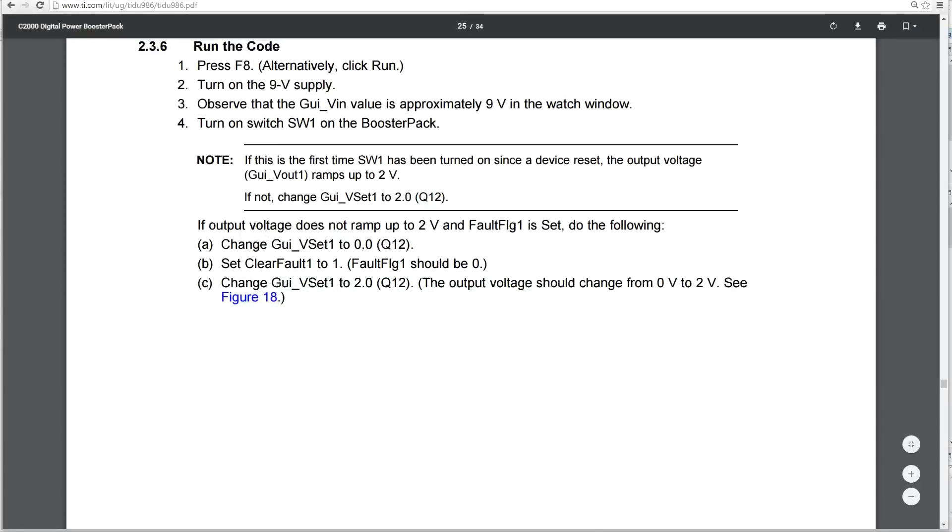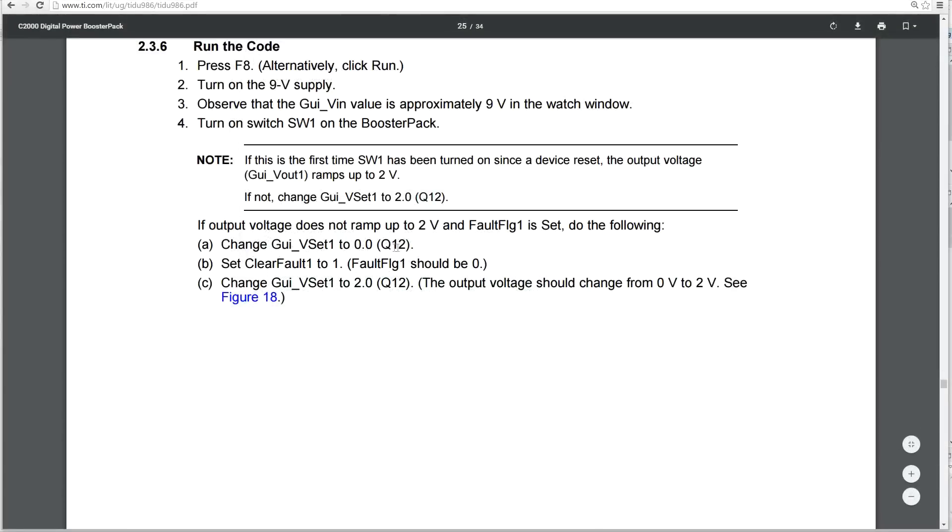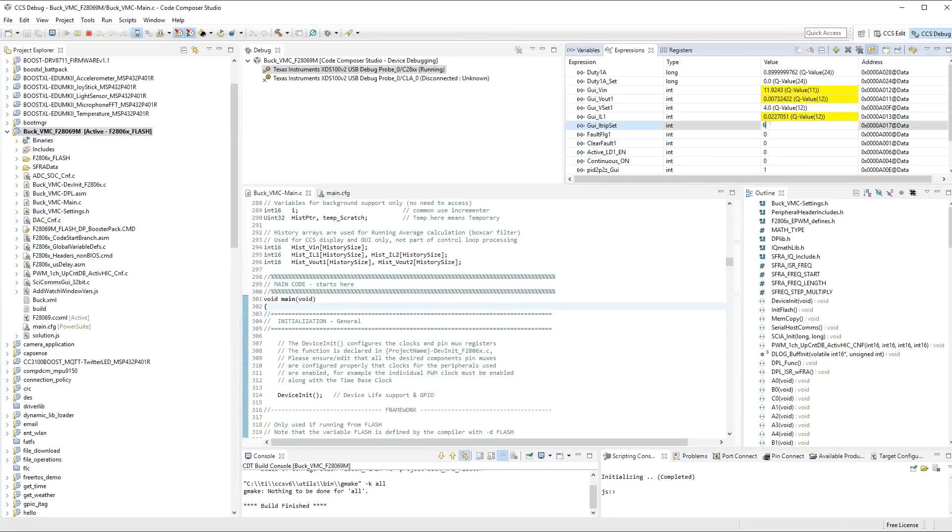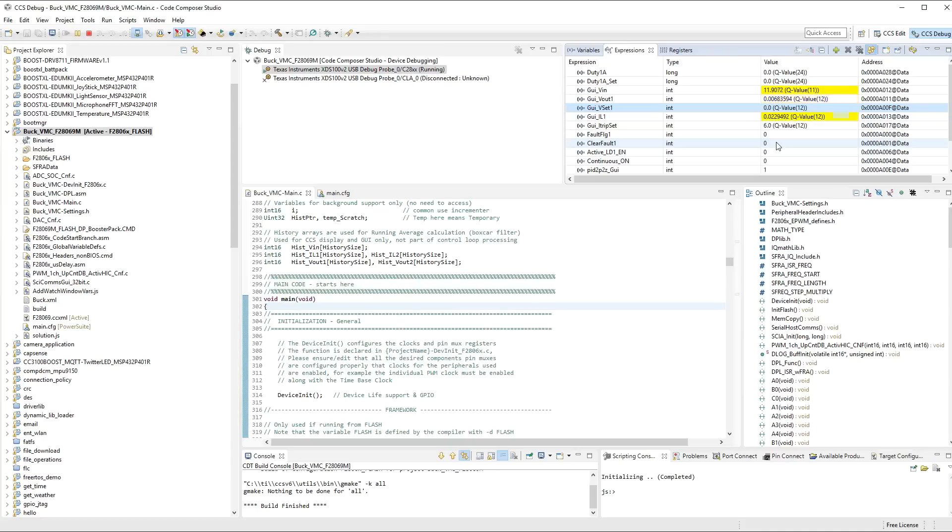Okay, to clear it now, I just had a quick check. You have to set the output voltage to 0 volts, clear the fault, and then change the output volts back to something that you want. So in here, this is still running. What I have to do is let's increase this current as well back up to 6 amps, of course. We set the desired output volts, which I've got here. We set to 0, clear the fault, which it already is. I did that before. And then you can turn the output on again, which is now on.